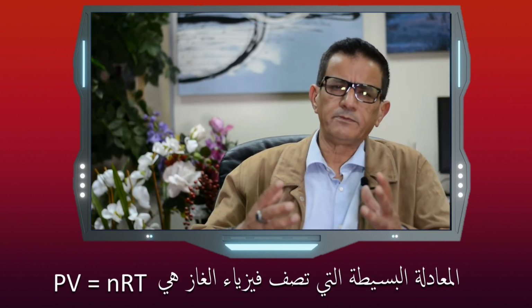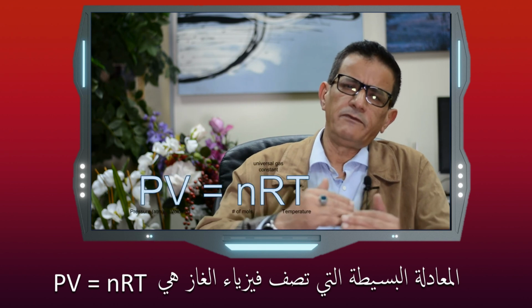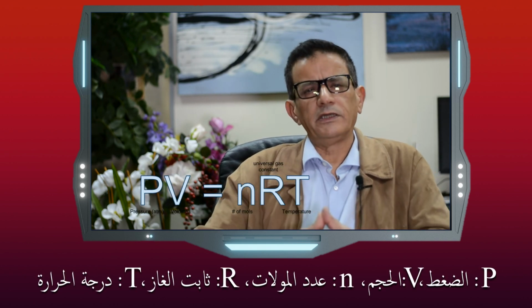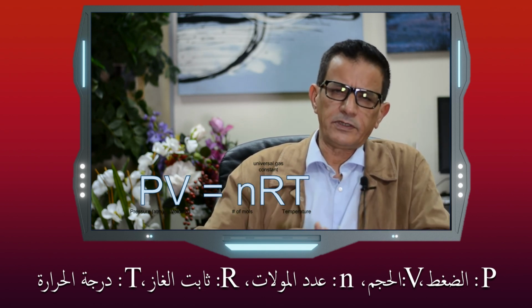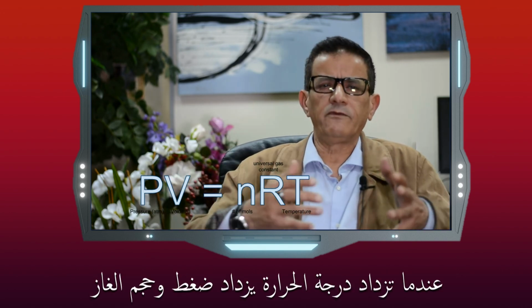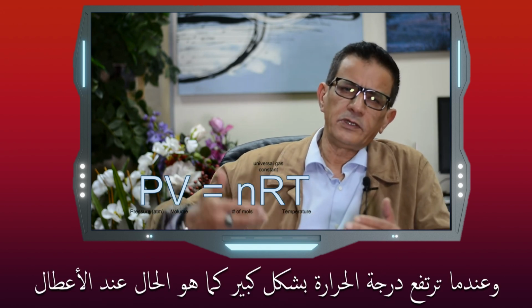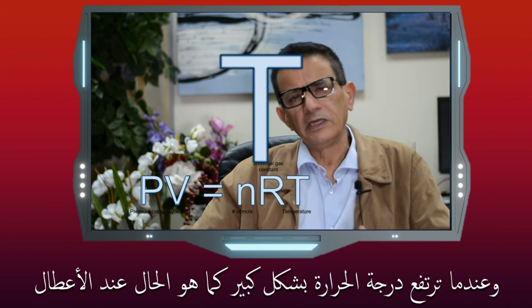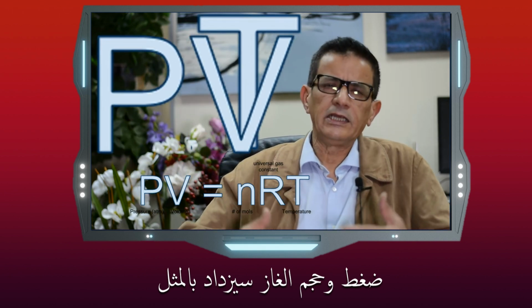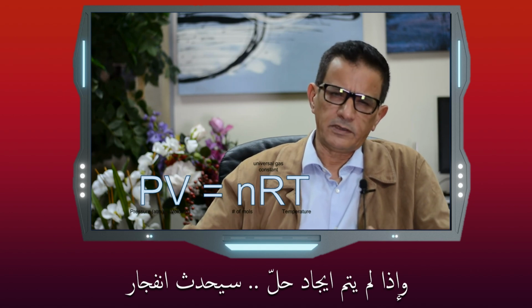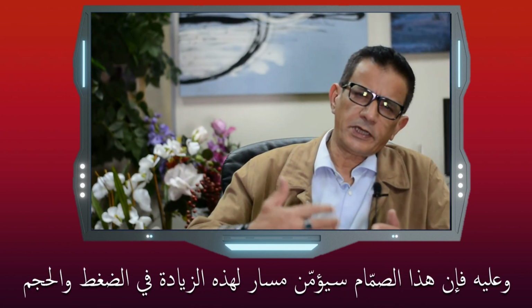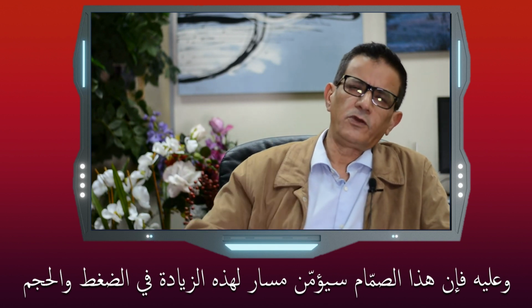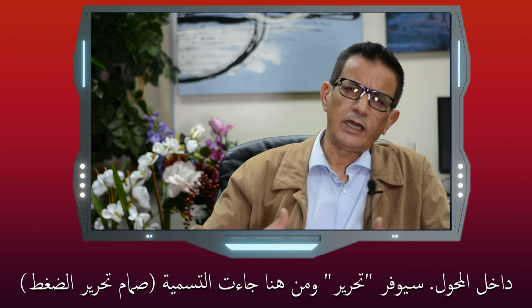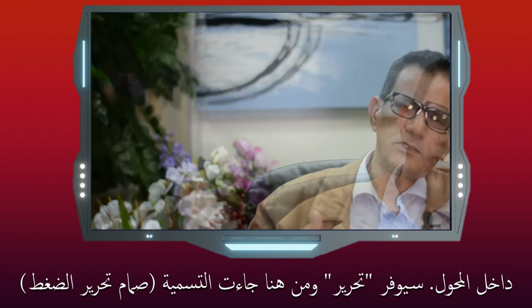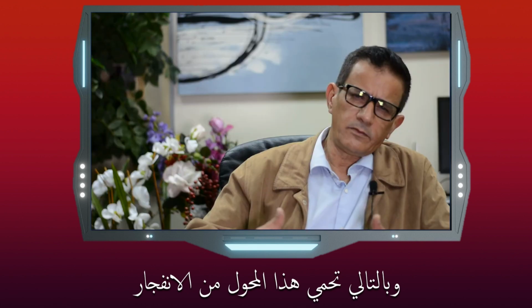The simple equation which describes the physics of the gas is PV = nRT. P is the pressure, V is the volume, n is the number of moles, R is the gas constant, and T is the temperature. When T increases, the pressure and the volume of the gas will increase. And when the temperature increases significantly, like in fault conditions, the pressure and volume of the gas will increase, and if it is not resolved, explosion will happen, and this is very dangerous. So this pressure relief valve will provide a route for this extra volume and extra pressure inside the transformer. It will provide a relief, and that's where the name comes from, and consequently protects this transformer from explosion.